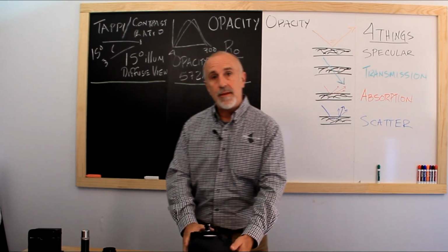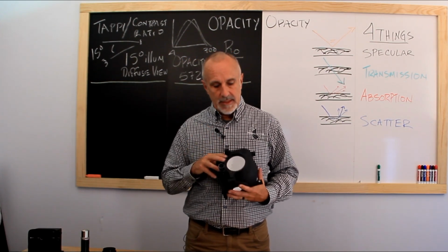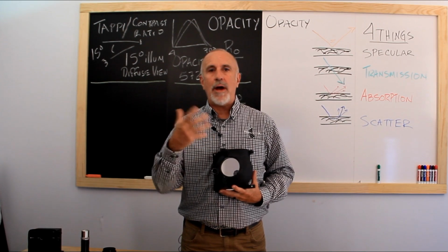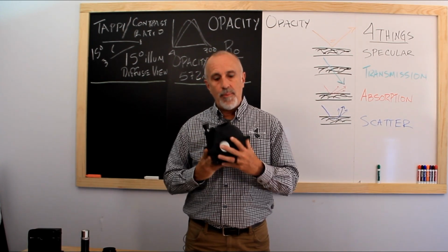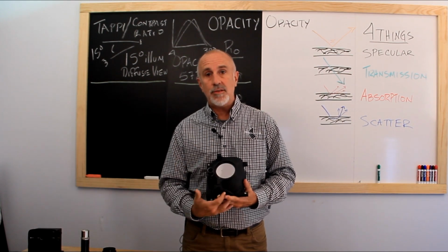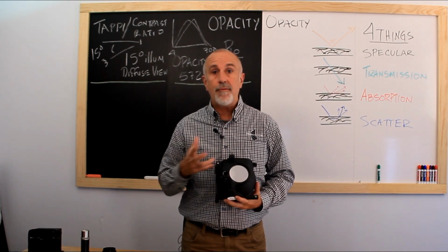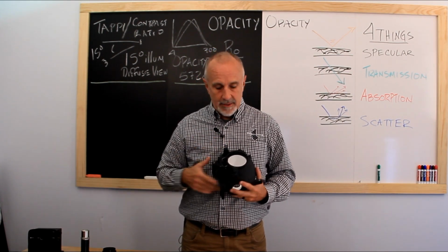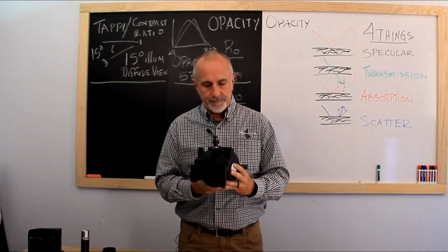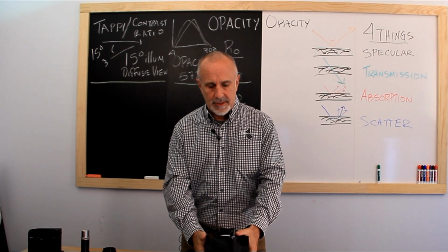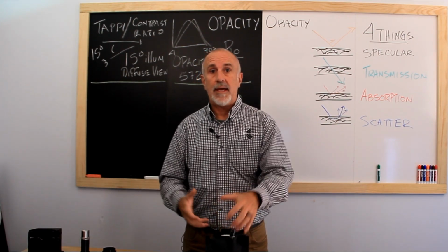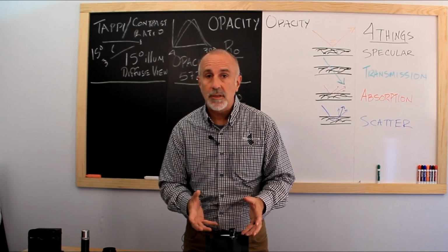And so with this, what you have is a sphere, and that sphere is coated with a very high reflectant matte white coating. Okay, so the goal is that if this is my light source that sits here, light shines into the sphere, light bounces off the sphere walls, and as that light illuminates the sample which sits here, the energy striking that sample is going to be equal from all angles. Okay, so it's going to have a diffuse illumination.